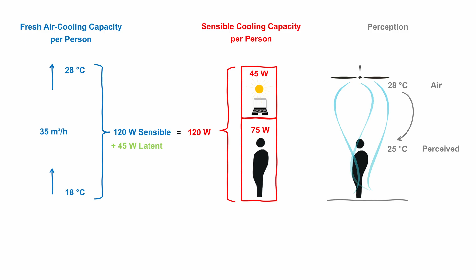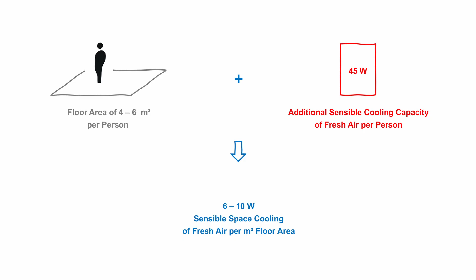At 4 to 6 square meters per person, this yields about 6 to 10 watts per square meter of sensible cooling. Though modest compared to full air conditioning, it is significant in buildings with efficient envelopes, low solar gains, and reduced loads, as in the School of Design number 4.